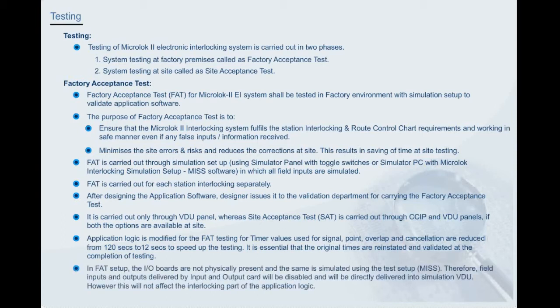In factory acceptance test setup, the input-output boards are not physically present and the same is simulated using the test setup MISS. Therefore, field inputs and outputs delivered by input and output card will be disabled and will be directly delivered into simulation visual display unit. However, this will not affect the interlocking part of the application logic.